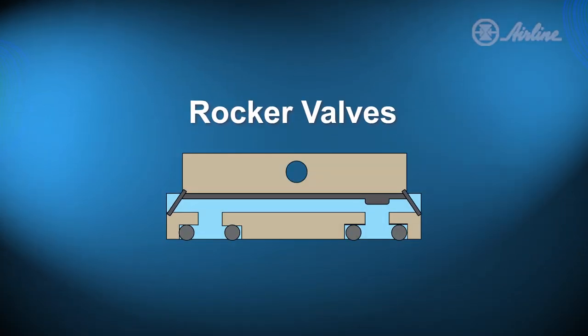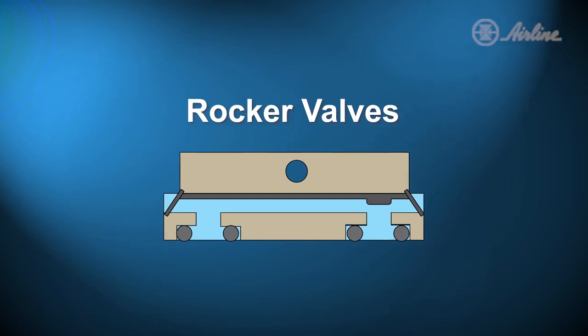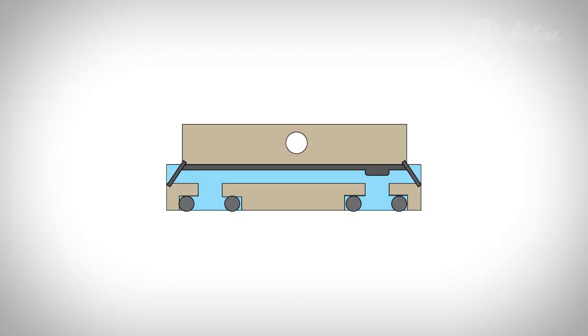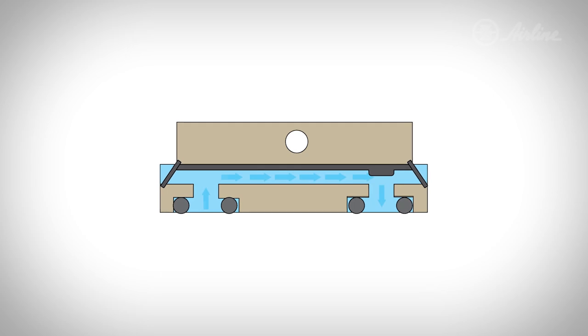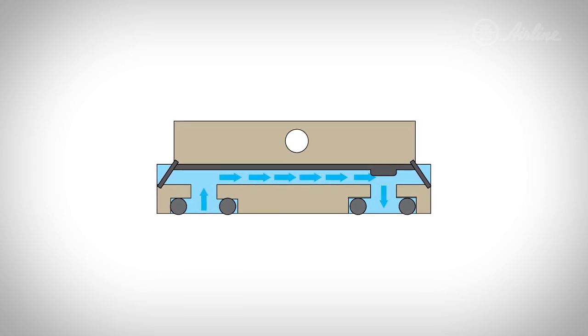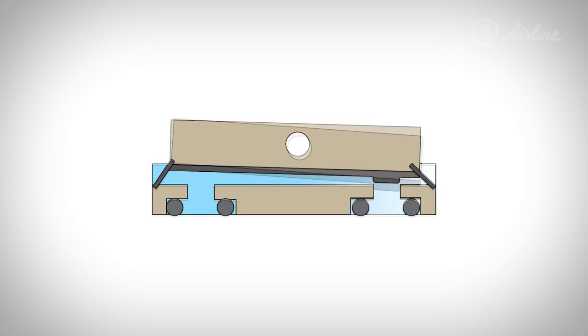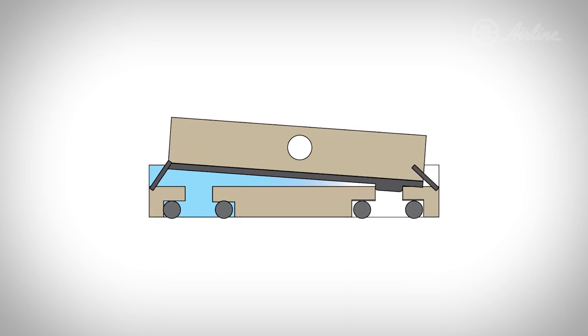First we'll explain rocker valves. A rocker isolation valve is a solenoid-operated device. As the name suggests, it uses a pivoting rocker mechanism to seal the valve seat and isolate the flow path. In this illustration you see a non-activated rocker valve along with the flow path of the medium. As the rocker mechanism is activated it seals the valve seat and isolates the flow path.